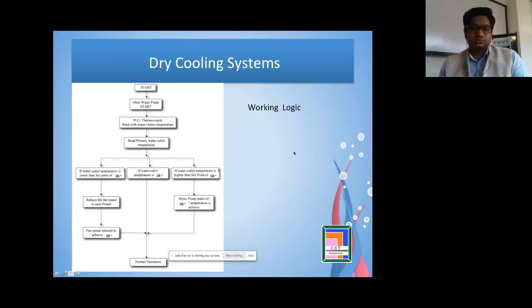So how the logic is working for the dry and adiabatic cooler. See, what happens is we start the system, the main water pump starts, which starts circulating in the heat exchanger. PLC reads what outlet temperature is there. Maybe when we start, it is like 25, 26, 27 degrees. It is close to ambient. So the water circulates for a few minutes. So what happens is the thermocouple will read.